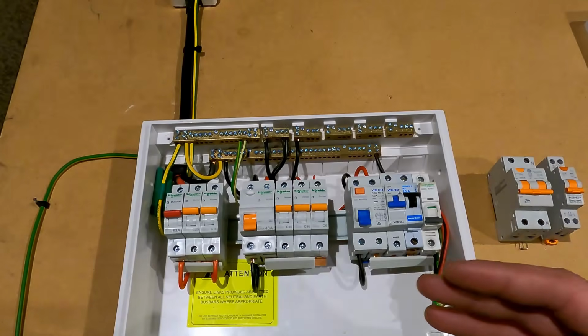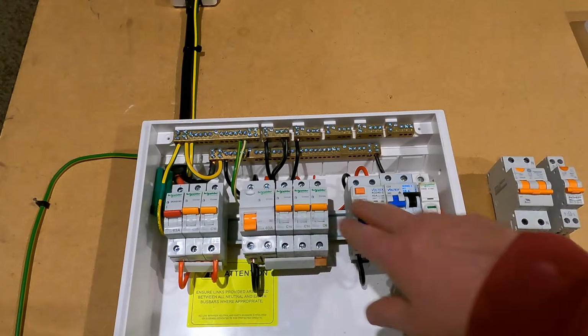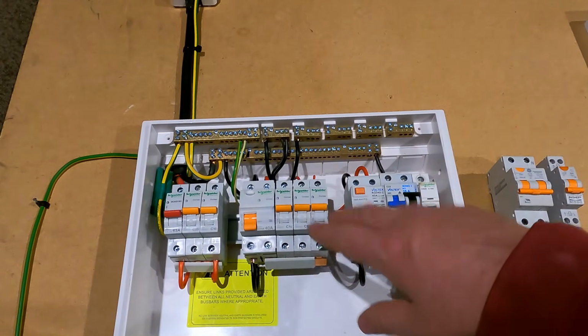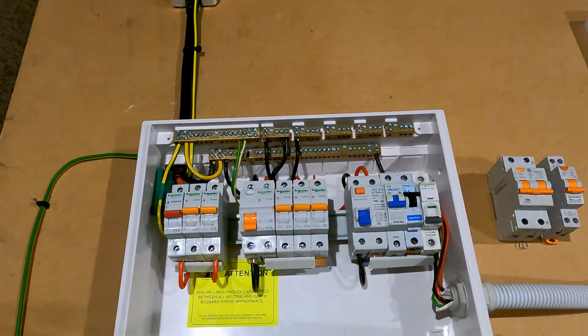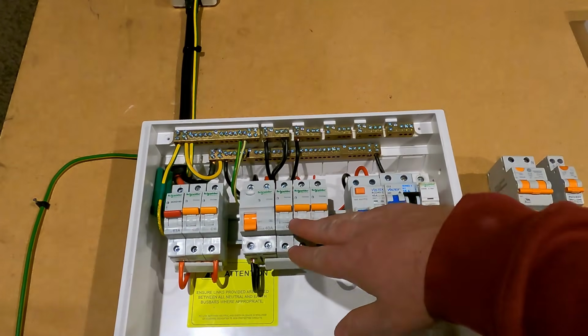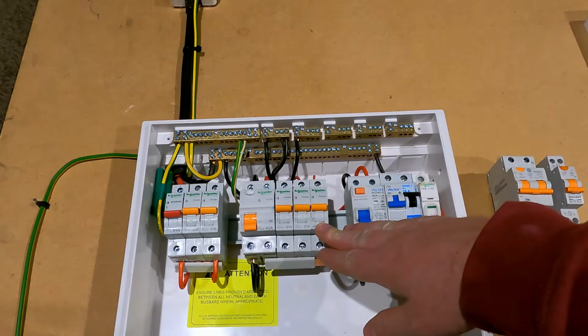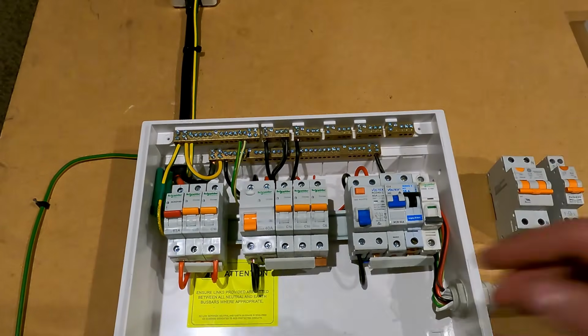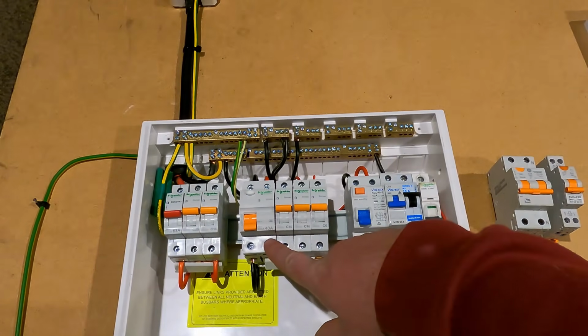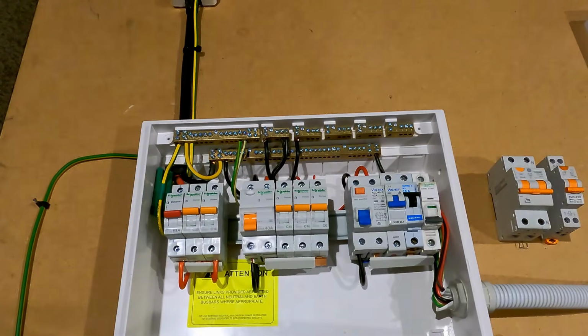The next thing we want to look at is the characteristics of the RCDs and their loadings to make sure they are compliant. Maximum demand actually says that the sub-circuits must be equal to or less than the maximum current rating of the RCD.